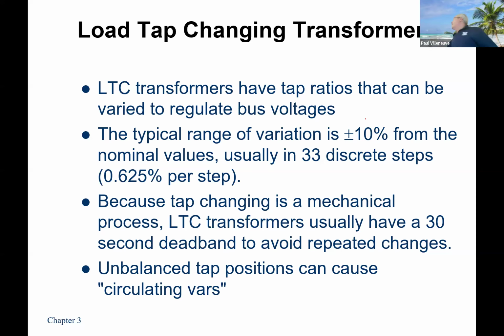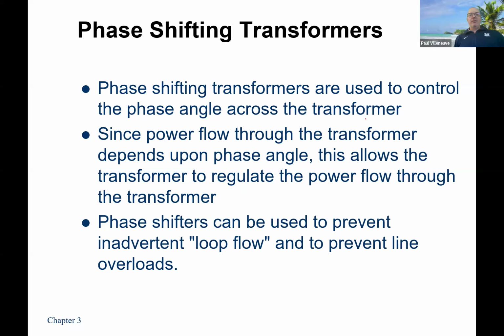But it's a mechanical process. And that means every time you do a tap change position, you're putting wear and tear into your system. So you try as much as you can not to have cycling of your tap changer. So you have that 30-second deadband saying, okay, the voltage is low or high for at least 30 seconds. Then I adjust, because if it's been there for 30 seconds, it's most likely not a motor that's starting, or somebody switched off a motor. It's going to be more of a longer term one. And you don't have to worry too much about unbalanced tap positions, because most manufacturers have a mechanical linkage between positions so that they're always in the same position.